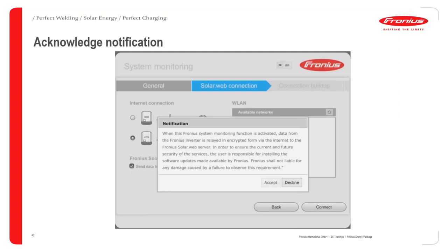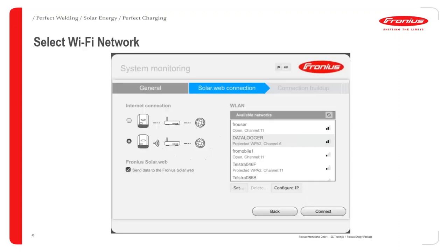You've set that up, and it's basically going to do the calibration charge, and depending on how you've got the settings set, if you can charge from the grid or not, then this may take a few hours. Okay, once you've done that, that's the technician wizard set up, and you'll see there'll be a tick next to the little man there on the screen. Then you want to go and start doing your Solarweb wizard, so you can actually see the monitoring on the site, so you can see what's going on on Solarweb.